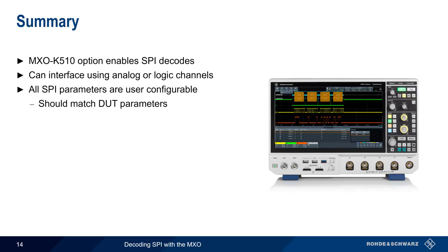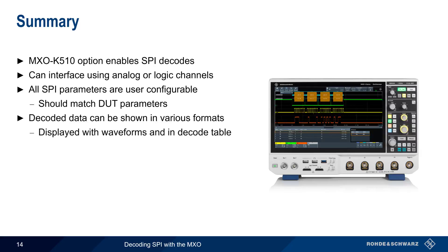Let's end with a brief summary. The K510 Serial Decode option enables SPI decodes on MXO Series Oscilloscopes. Connections to the DUT wires can be made either using the scope's analog channels or using logic channels. All SPI protocol parameters are user configurable and should match the DUT parameters. Decoded serial data can be displayed in a variety of formats such as hex, binary, ASCII, etc., and this data is displayed both with the waveforms and in a decode table.